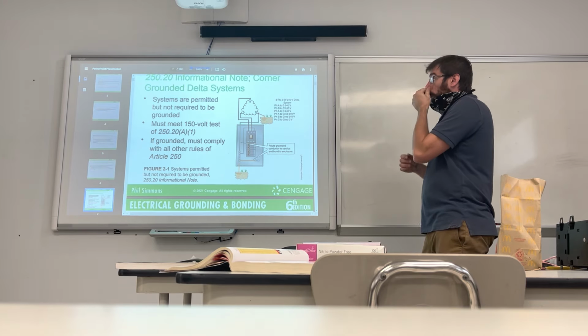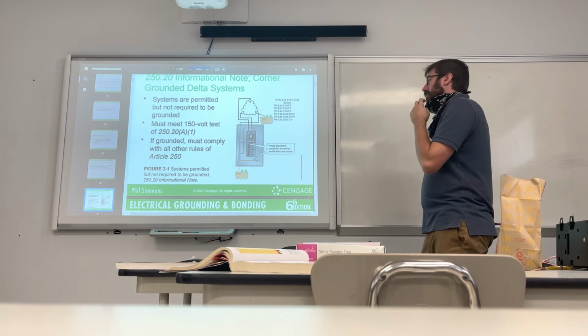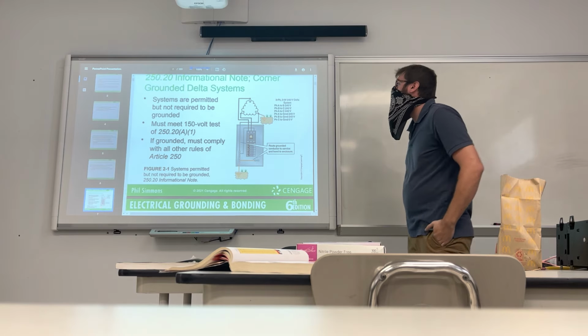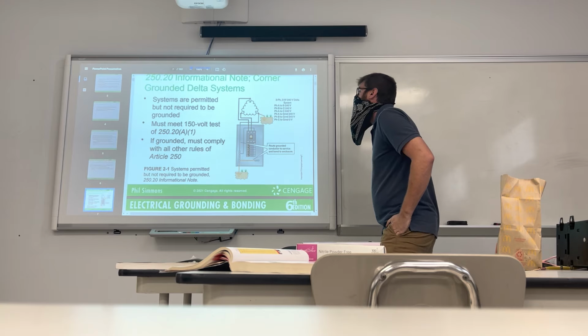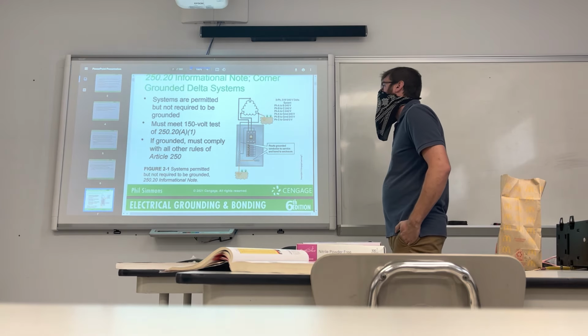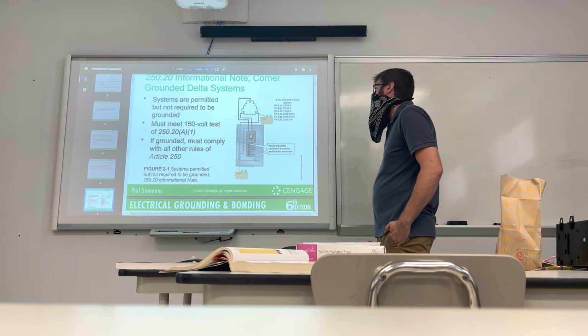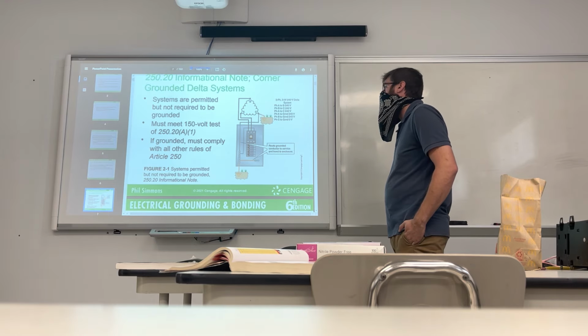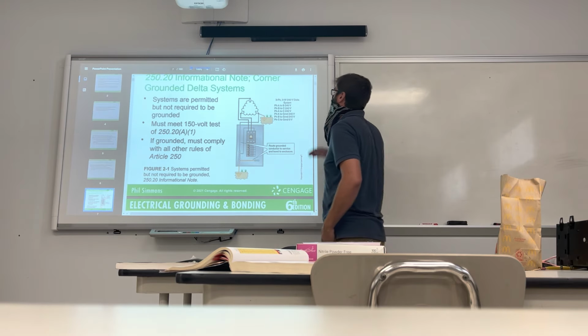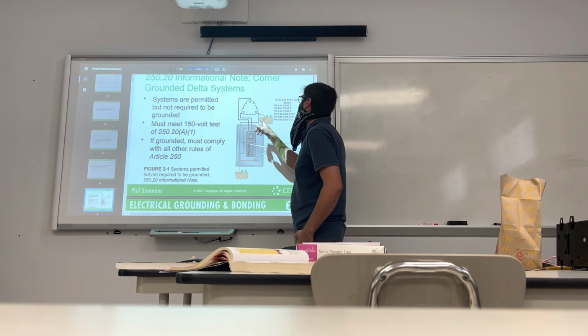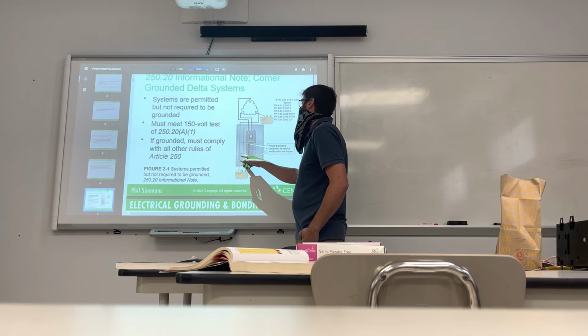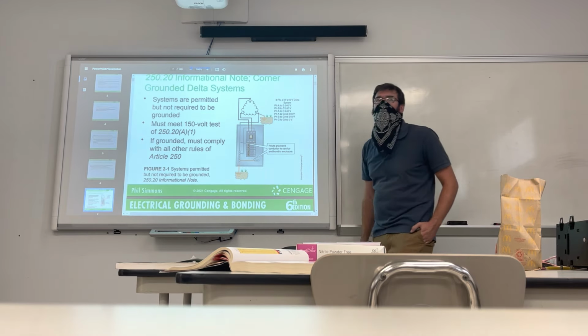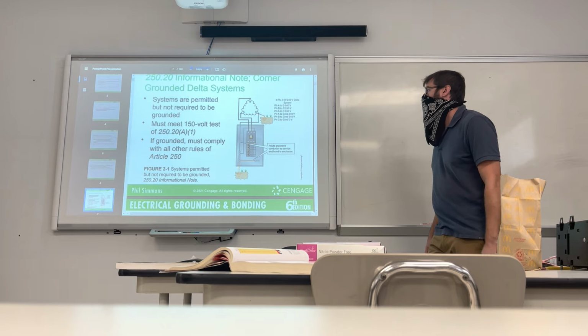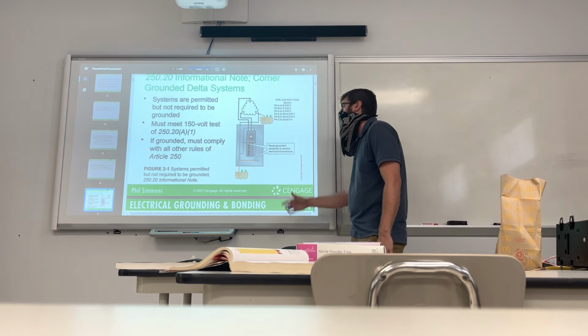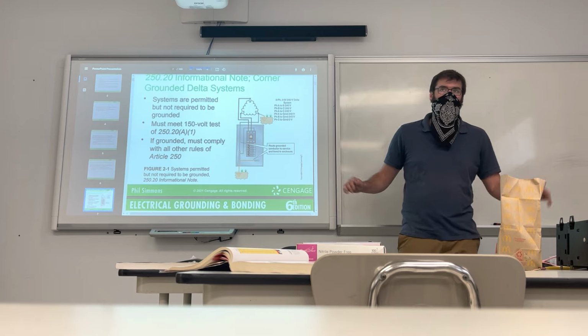Informational note, corner grounded delta systems. Systems are permitted but not required to be grounded. Must meet the 150 volt test of 250.20(A)(1). If grounded, must comply with the other rules of Article 250. Yeah, this is an odd duck, and you're not going to see this too often, but phase C is just a neutral phase. Very rare, very odd. I doubt that you'll even see this in the real world, but just note that this is a possibility. Not likely at all, but it is a possibility.